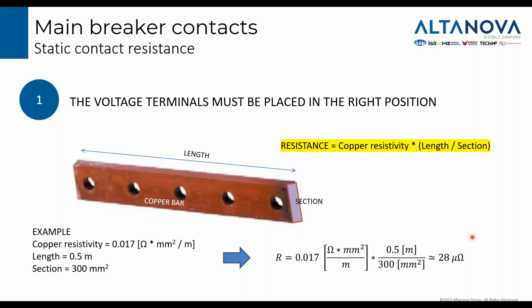Now we explore why the position of the clamps is very important. Let's imagine using a copper bar, and we want to measure its resistance. The resistance of this copper bar is defined in this way. You have a number that represents the copper resistivity. The longer the bar, the higher the resistance. The wider the section, the lower the resistance. If we input some reasonable numbers in this formula, we can get a reasonable value of resistance. In this example, we have, let's say, 28 microohms.